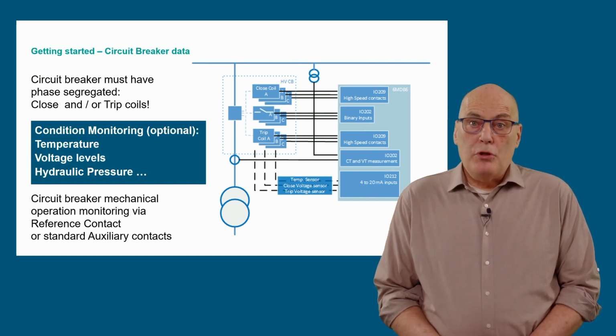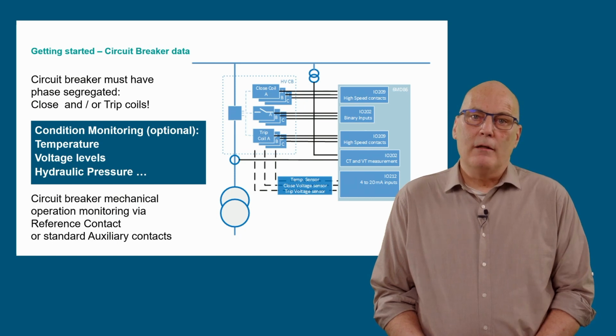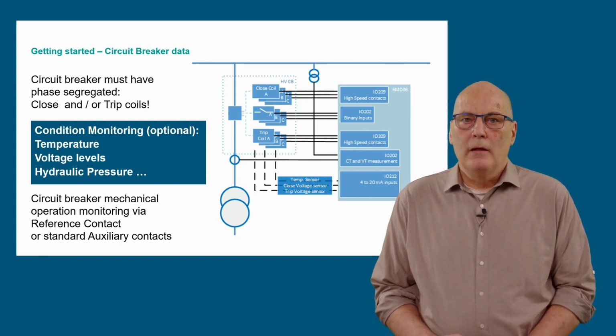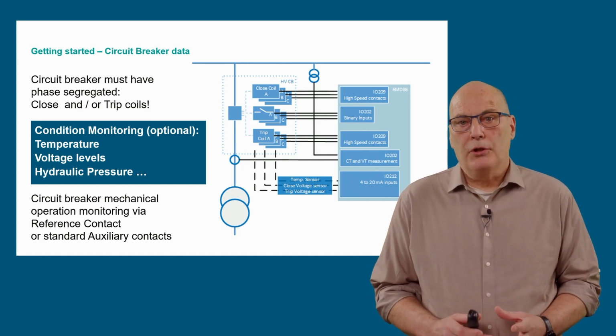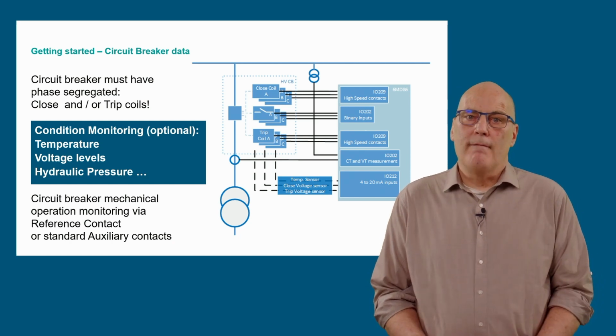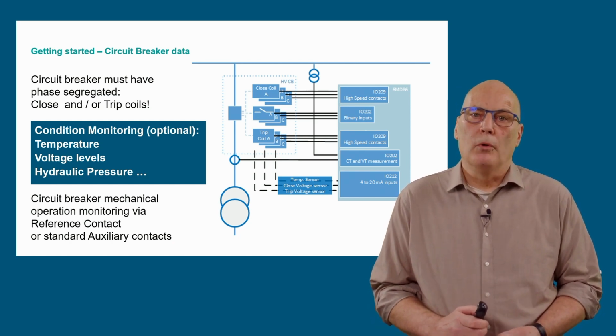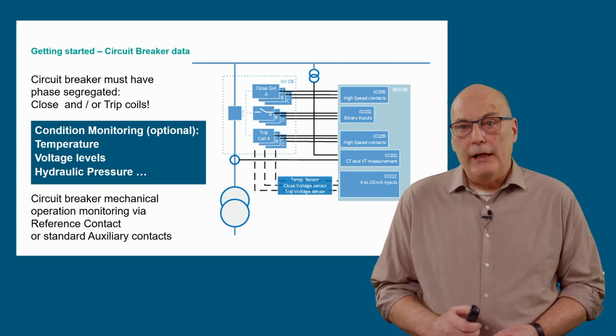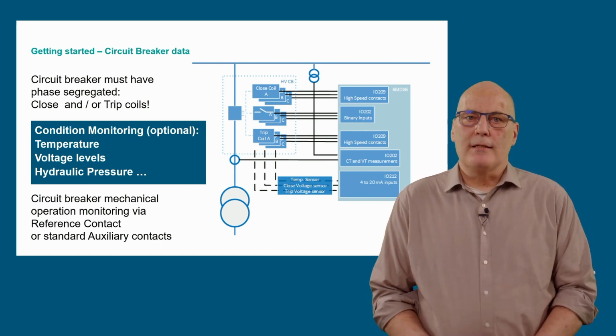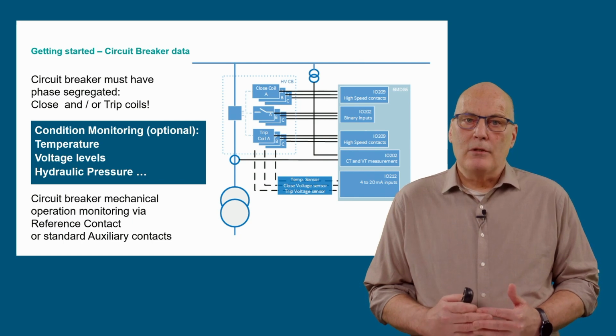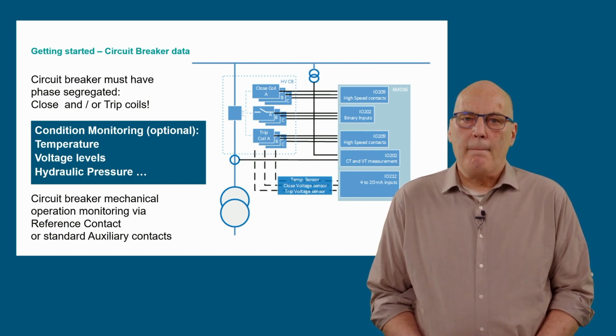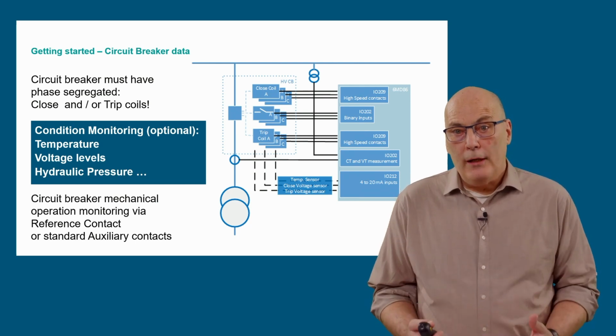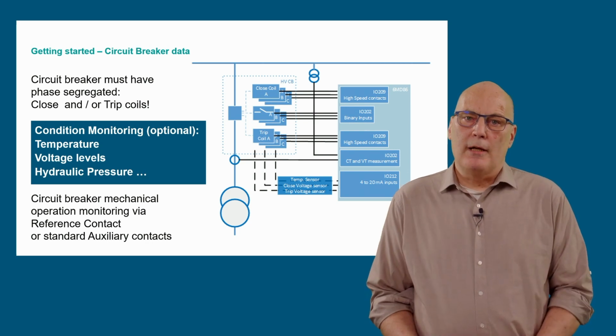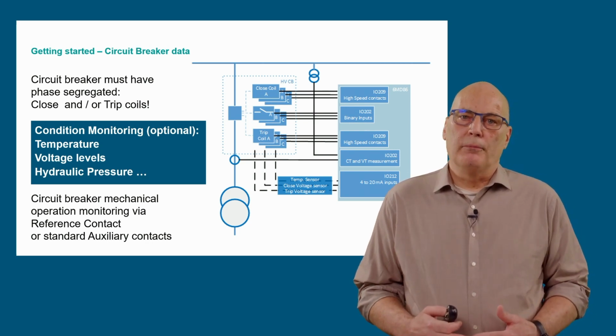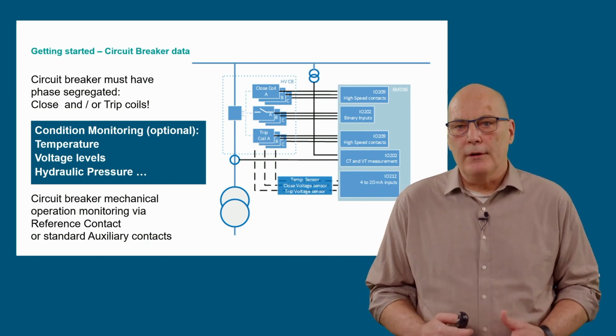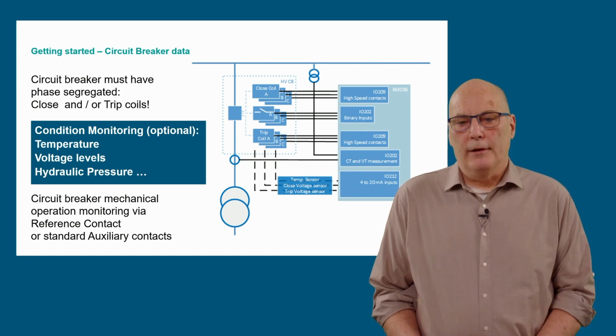The mechanical circuit breaker position during switching can be obtained with standard auxiliary contacts via binary inputs. If the breaker has a reference contact with more accurate switching position status, this can also be implemented via transducer input on the IO212 module. It will be shown later how this information is used during commissioning to check and adjust the function. The circuit breaker response time is of central importance to the point-on-wave function. If conditions such as ambient temperature, hydraulic pressure or control voltage have an impact on the response time, this may be compensated in the point-on-wave function. For this purpose, these conditions can be monitored via transducer inputs, as shown at the bottom of the diagram.